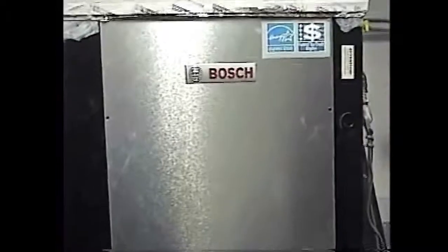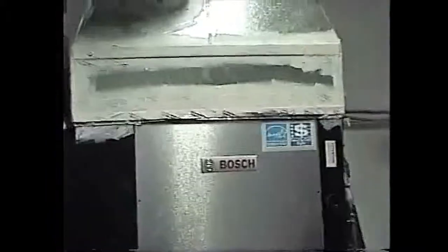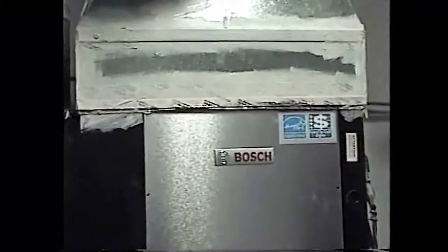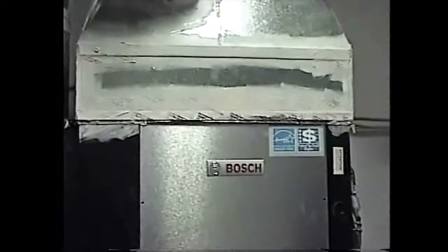It's not some chiphead sitting back in the factory saying, well, okay, after 2.5 minutes we'll do this, or after 3 minutes we'll do this, and then we'll see what happens, and you should like it. This is like spoon feeding a baby. It's going to get exactly what it needs, all the time, at the right time, forever. I told Richard when I ordered this control, and this is another thing you can do with fan handler, you can tell them what you want the leaving air at maximum speed to be. Or I said, at 105-degree leaving air, I want the fan at high speed.